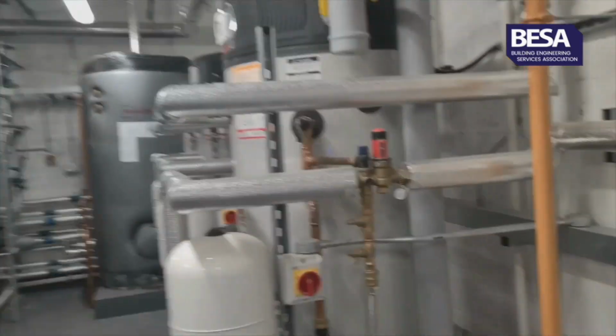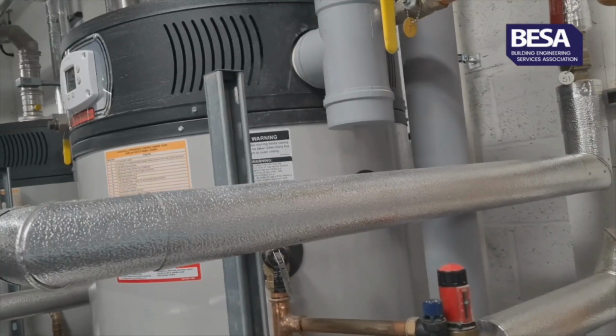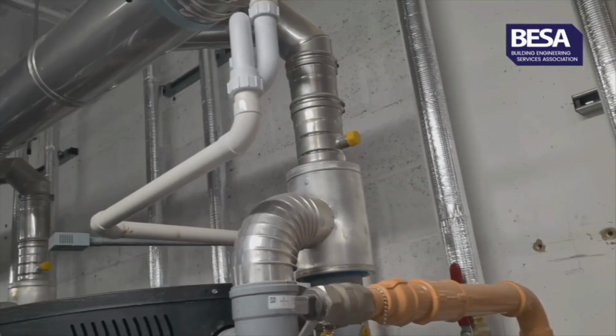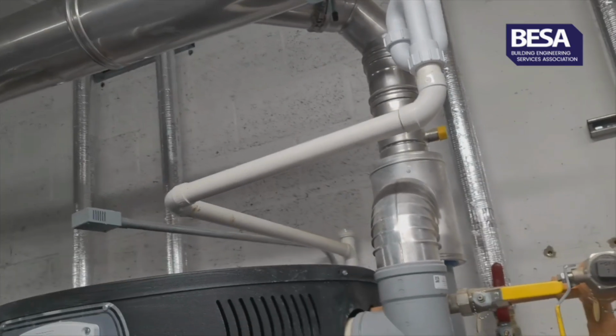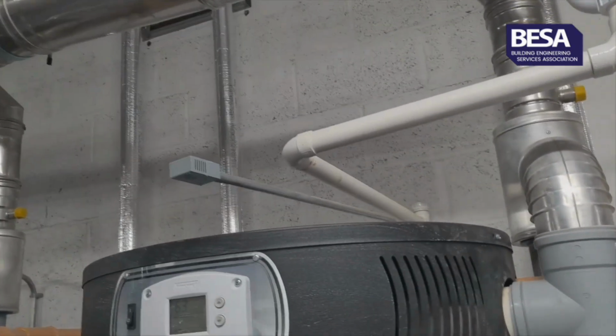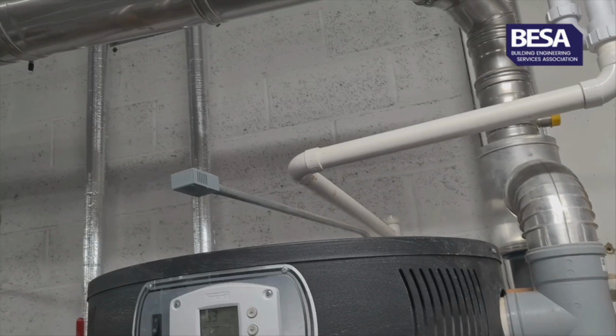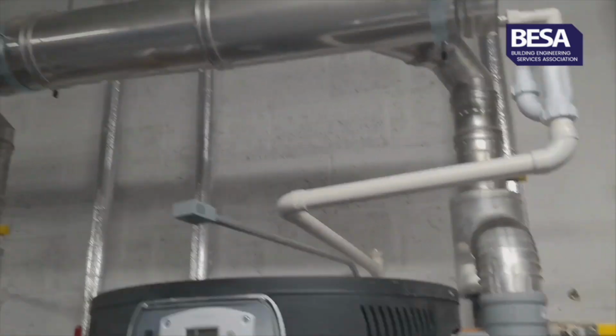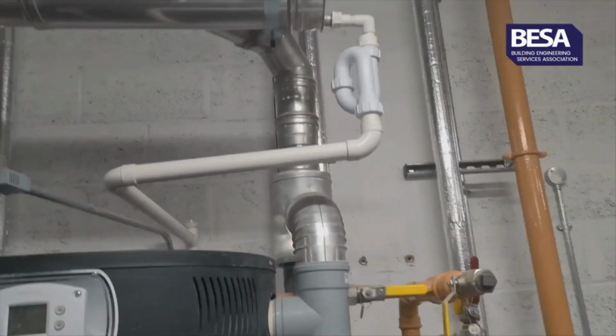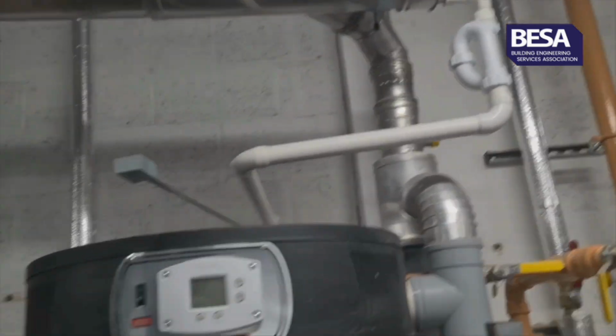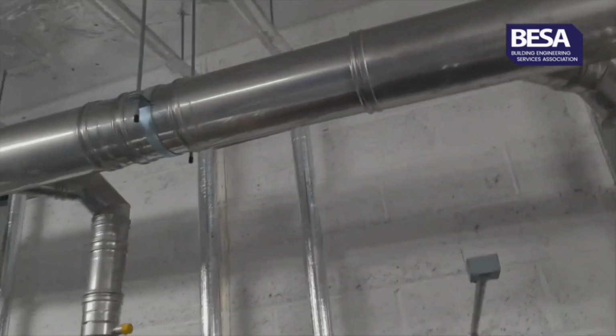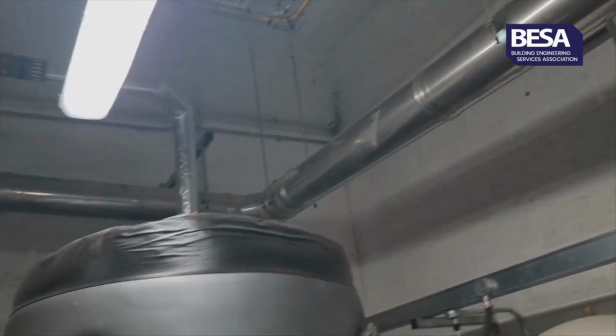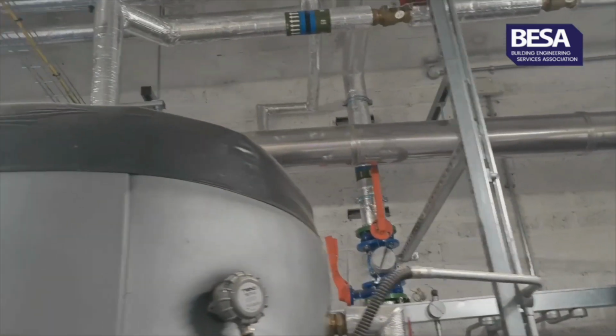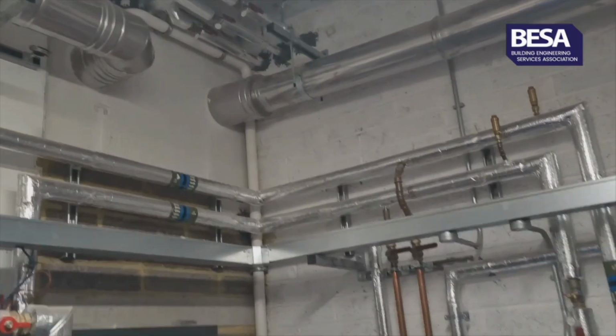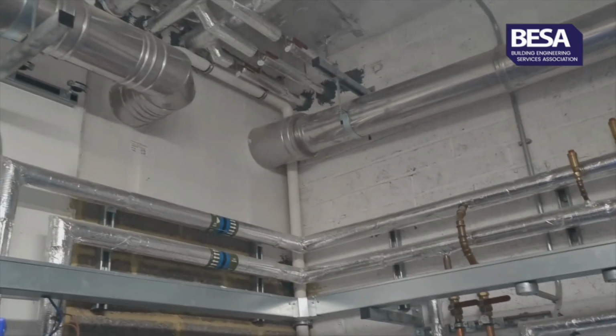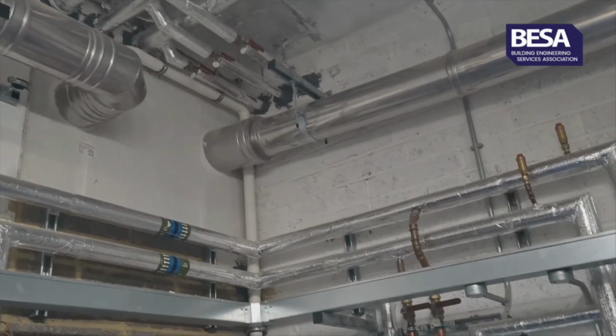Okay, going back to the gas-fired water heaters, these are the flue connections. So the flue has all been installed to conform with BS EN 1856 and BS 6644, Clean Air Act. You see, all well done. There's a track there as well. So our flue, again, all the certification for the flue is within the O&M manuals. As it goes through the wall here, it then goes into a riser, which is fully accessible, so you can carry out visual inspections.